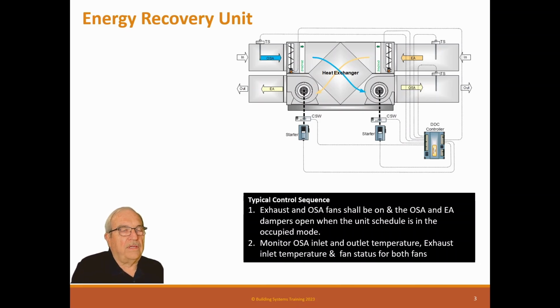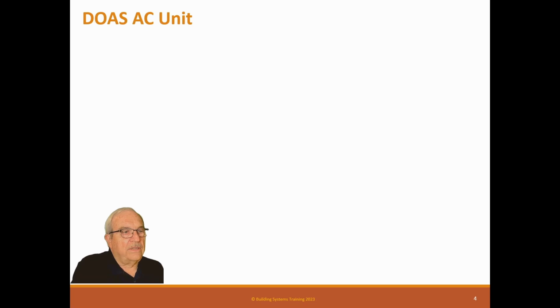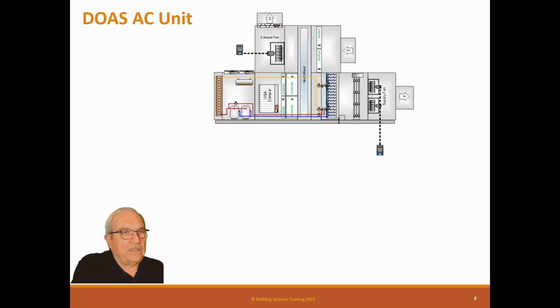Okay, now this is a dedicated outside air unit called a DOAS, and it's basically a bigger unit. This one happens to have a heat wheel for heat exchange in there. There is a little bit of a problem because it's an air conditioning unit. Air conditioning units cannot withstand very high ambient temperatures for 100% outside air flow. So if they're regular air conditioning on a building and they have 20% outside airflow, that'll work because the mixed air temperature is never that hot.